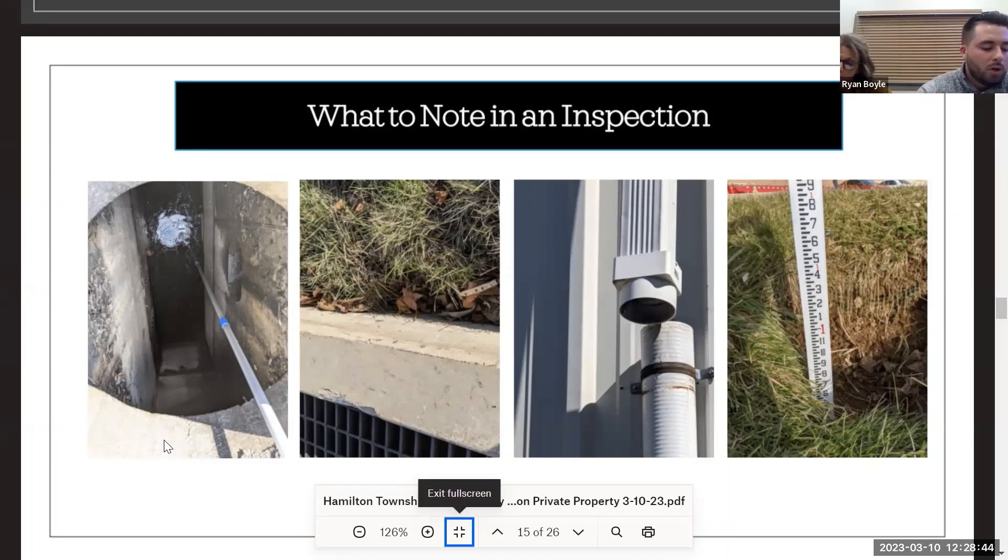It's common practice — if you see something, you want pictures, write it down. Recessing means ponding or standing water where it really shouldn't be, or a hole that wasn't naturally formed. You want to monitor it because the first glance might look okay, but two months later it could be growing bigger. That's why inspections let you nip it in the bud before it becomes a bigger problem.